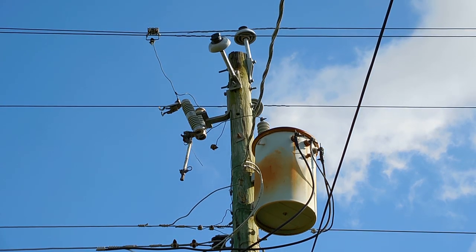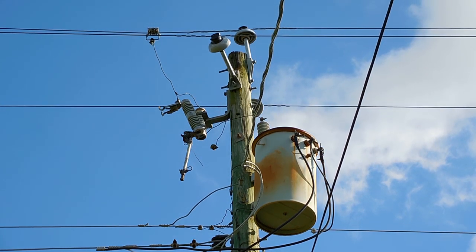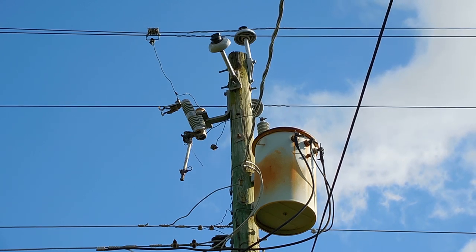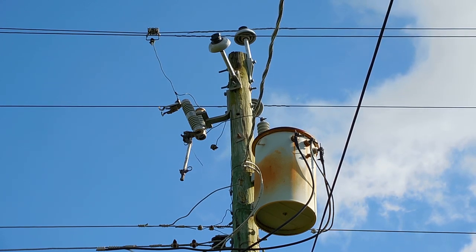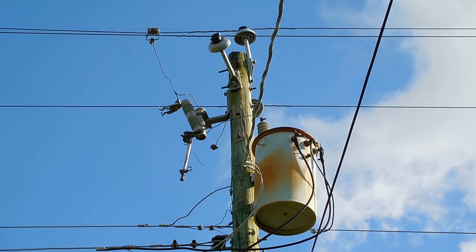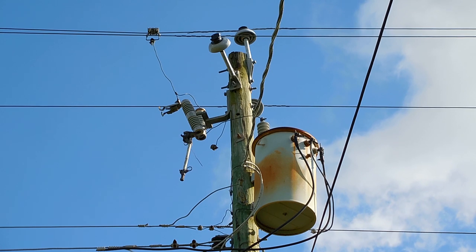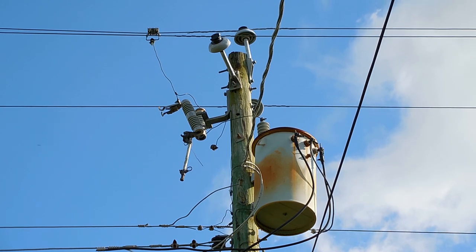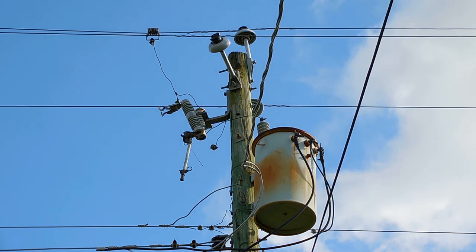All power was lost inside the house, so I went outside and checked the circuit breaker — that was on. So I looked at the utility pole, and I knew right away: you can see the switch is hanging in the down position. The circuit is open. We don't have any power flowing from the high voltage line at the top with the clamp into the transformer's primary winding. So I called up the utility company and they're sending somebody out to try resetting the switch.